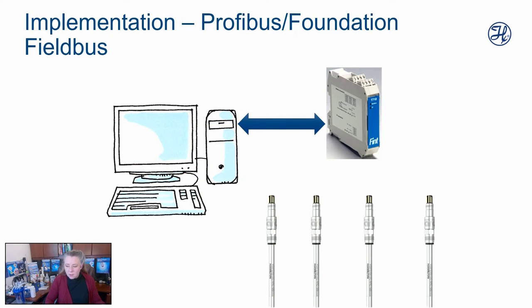4 to 20 is also an analog signal, but it's much more robust, and newer bioreactors either use a 4 to 20 or a Modbus or a Profibus or Foundation Fieldbus. And these are where you have to have an intelligent sensor that allows a digital signal output. Digital is very robust.